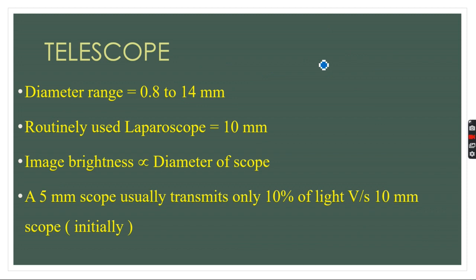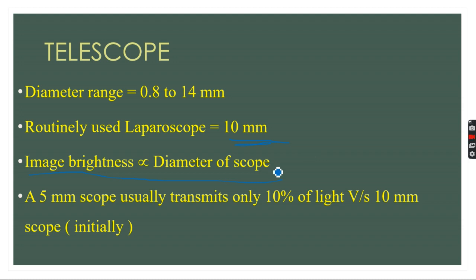The third important property of the telescope is the diameter, which ranges from 0.8 mm to 14 mm. In laparoscopy, the routinely used diameter for laparoscopic cholecystectomy or laparoscopic appendectomy is 10 mm. Remember that image brightness is directly proportional to the diameter of the scope — the brightness produced by a 2 mm scope will be less compared to that of a 10 mm scope. As the diameter increases, brightness also increases. For example, a 5 mm scope transmits only 10 percent of the light compared to the 10 mm scope.